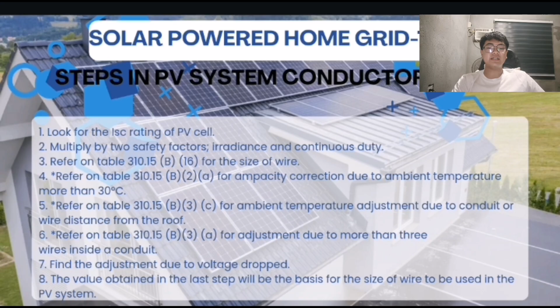So, 5. Refer on Table 310.15 B3C for ambient temperature adjustment due to conduit or wire distance from the roof. 6 is refer on Table 310.15 B3A. So, ito naman yung for adjustment due to more than 3 wires inside a conduit. Next is find the adjustment due to voltage drop. 8. The value obtained in the last step will be the basis for the size of wire to be used in the PV system. So, next naman, yung nakikita dito ang spec ng dalawang magkaibang solar. So, ito yung two different solar panels.